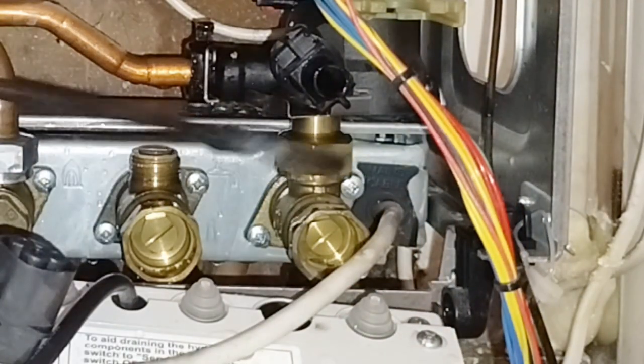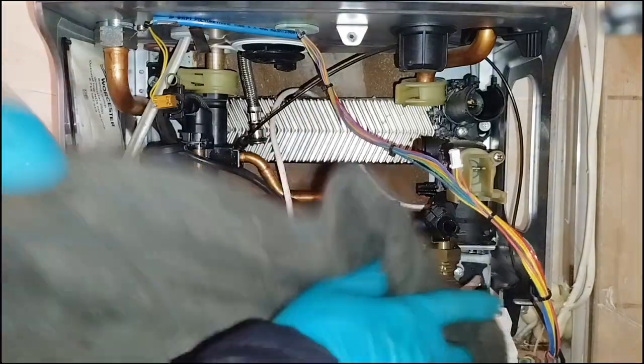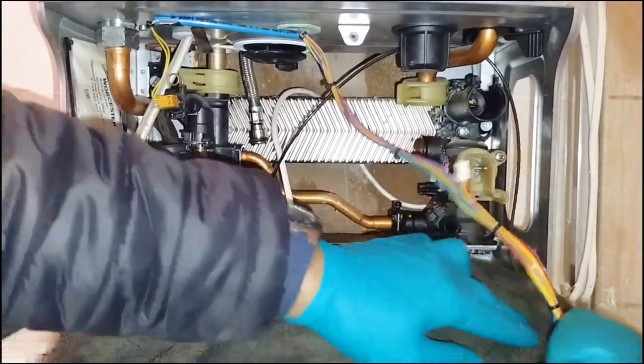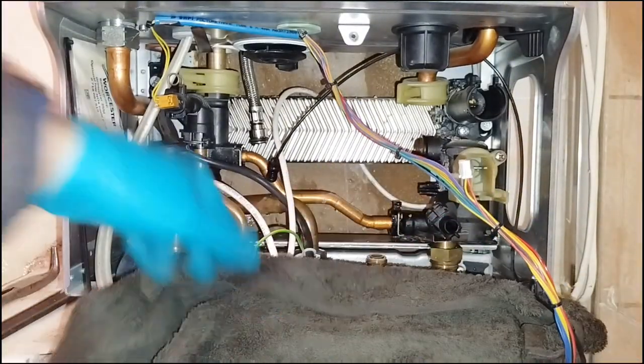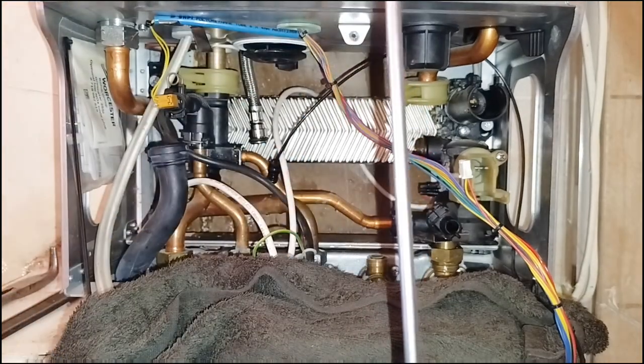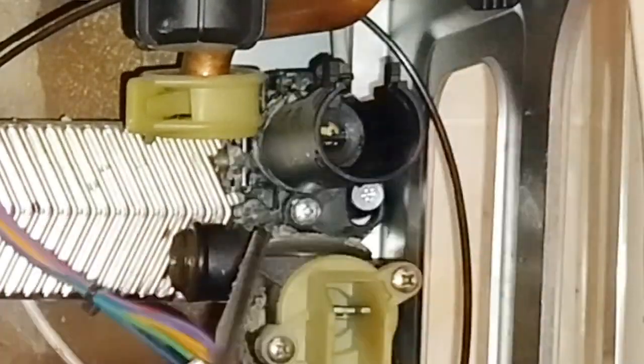After that, the nut on the return pipe, which comes from the heating return, loosen it up. After that, what we're going to do is obviously cover the back of the PCB, the circuit board assembly, and take a long crosshead or Phillips screwdriver and undo the two screws. This one is holding the plate heat exchanger in position, loosen it up completely, and then the second screw which sits next to it is the one which is actually holding the return assembly in position.